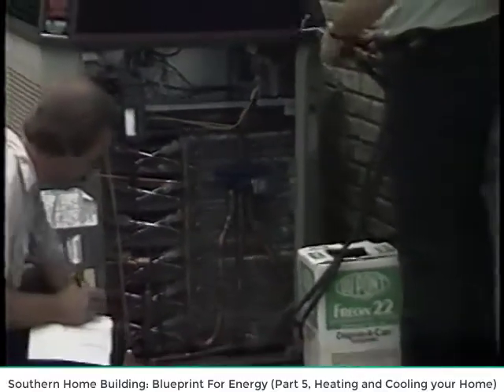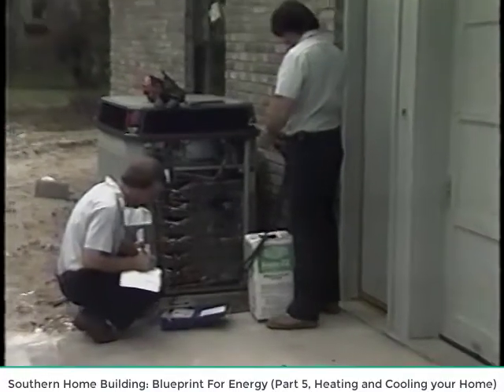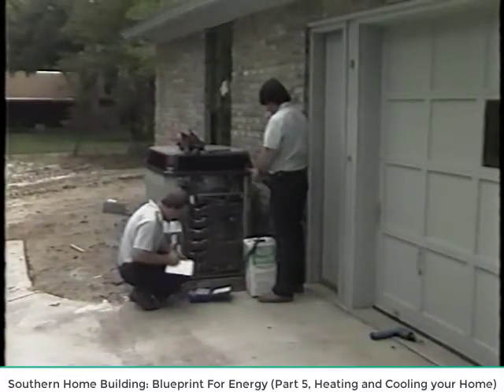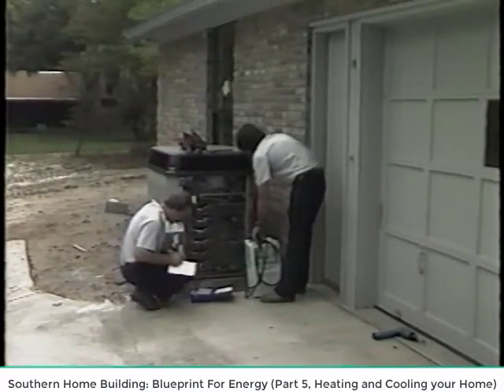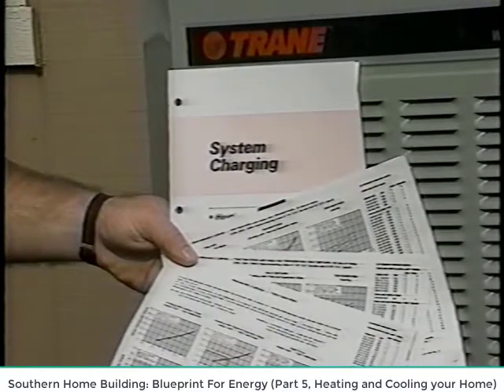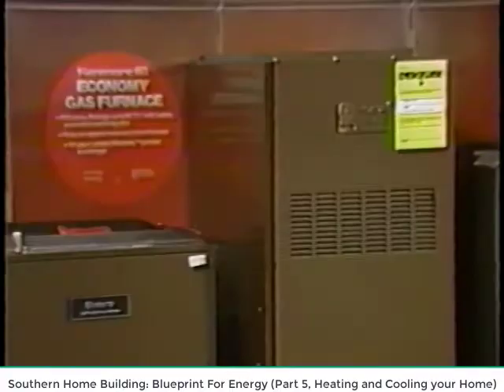Surprisingly, as much as 50% of the efficiency of a heat pump can be lost if it is charged with the wrong amount of refrigerant. Charging procedures and pressure charts from the manufacturer must be used. If the wrong amount of refrigerant is used, not only can the efficiency drop, but the tonnage can drop and the heat pump will wear out sooner, perhaps even years sooner. If natural gas is available in your area, a natural gas furnace with electronic ignition is a good investment, equivalent to an investment in a heat pump.